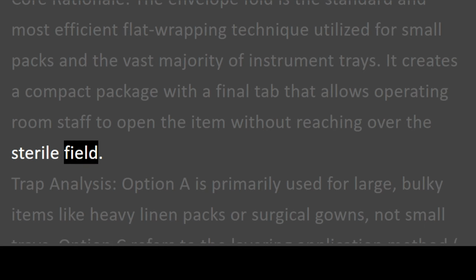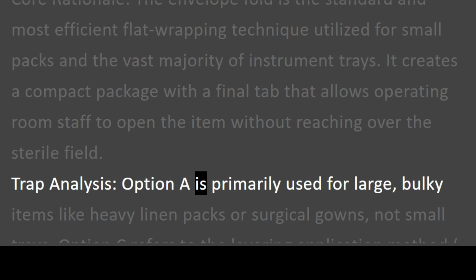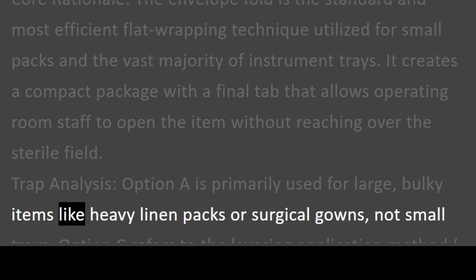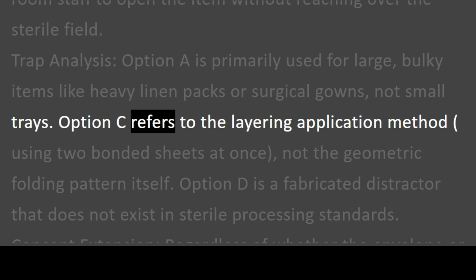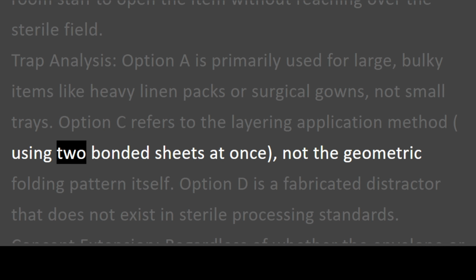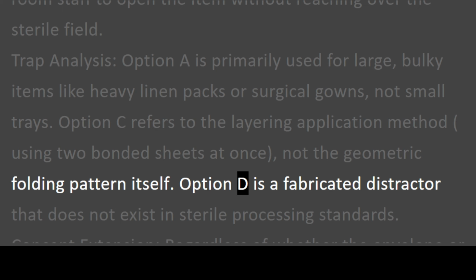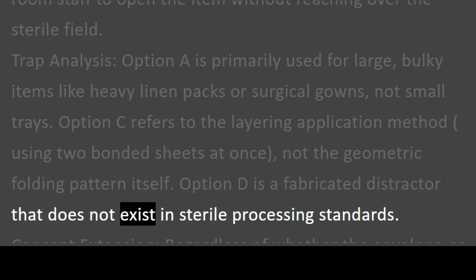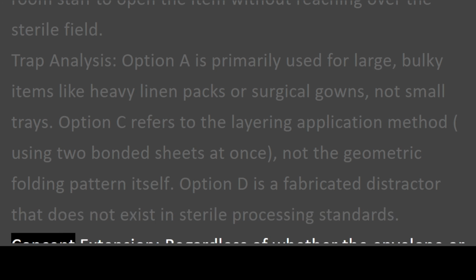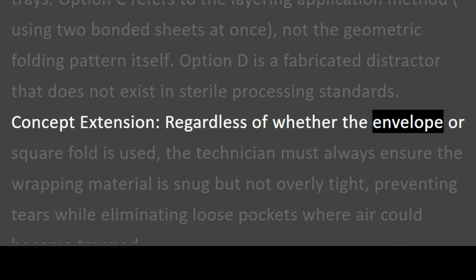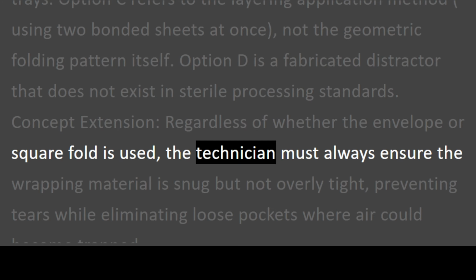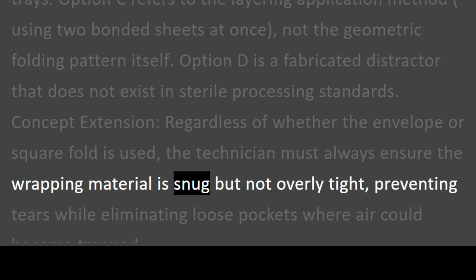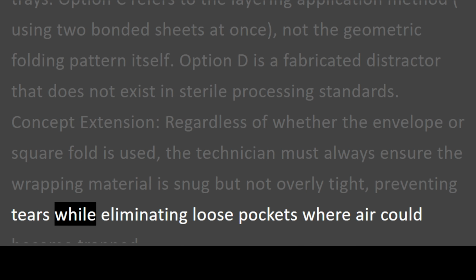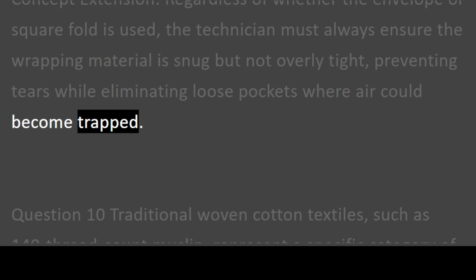Trap analysis: option A is primarily used for large, bulky items like heavy linen packs or surgical gowns, not small trays. Option C refers to the layering application method, using two bonded sheets at once, not the geometric folding pattern itself. Option D is a fabricated distractor that does not exist in sterile processing standards. Concept extension: regardless of whether the envelope or square fold is used, the technician must always ensure the wrapping material is snug but not overly tight, preventing tears while eliminating loose pockets where air could become trapped.